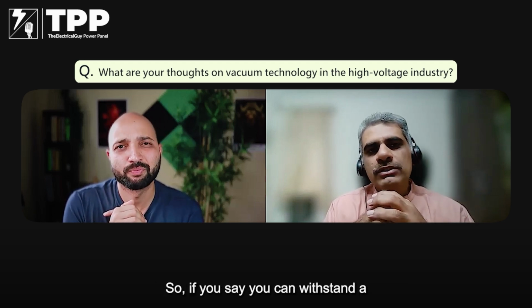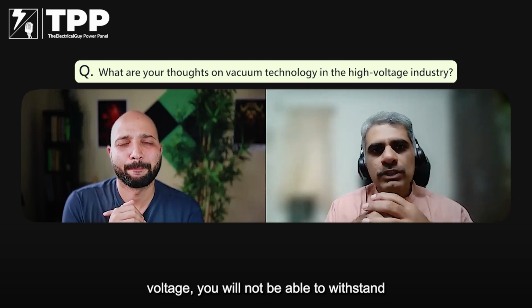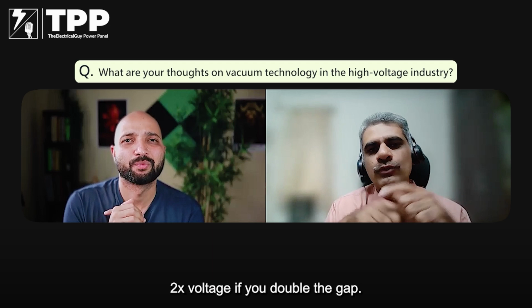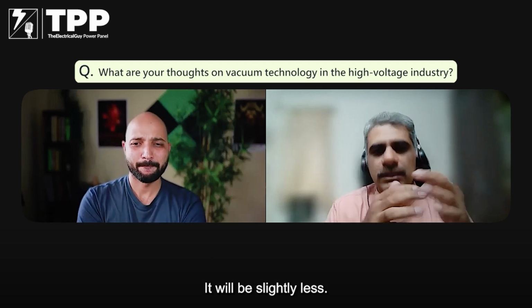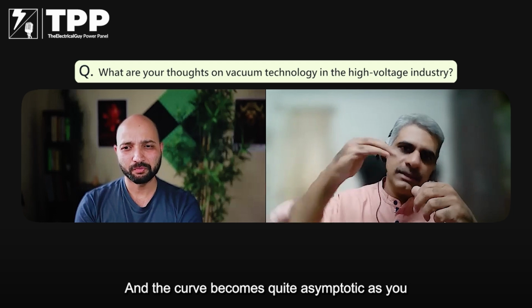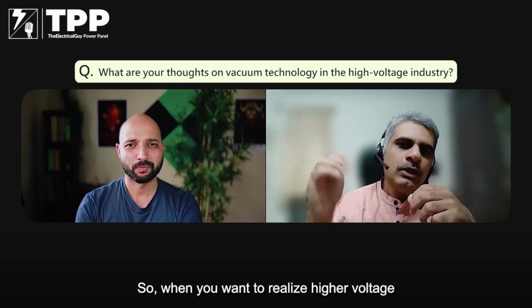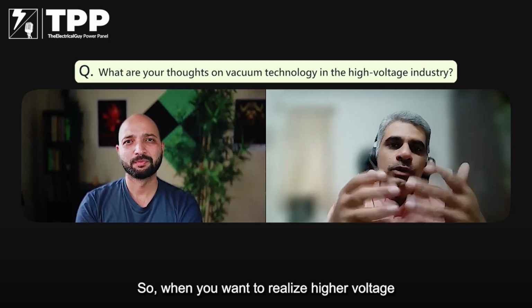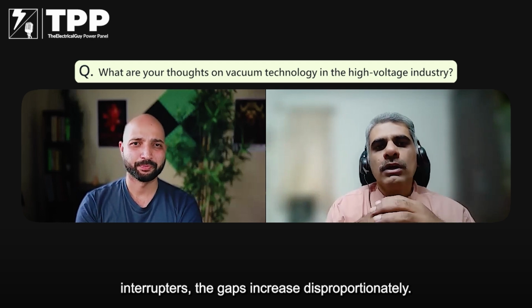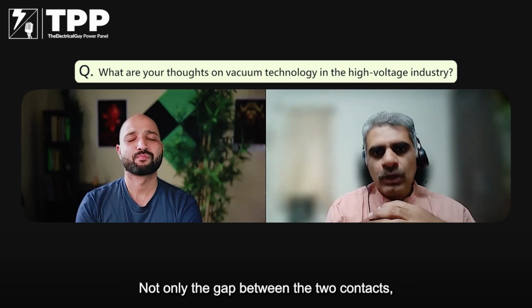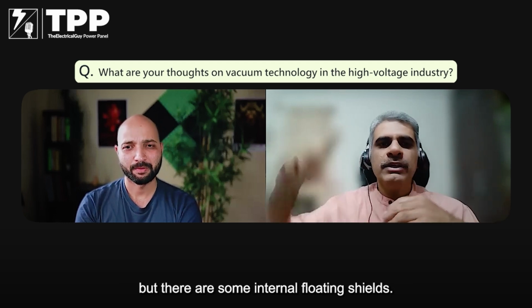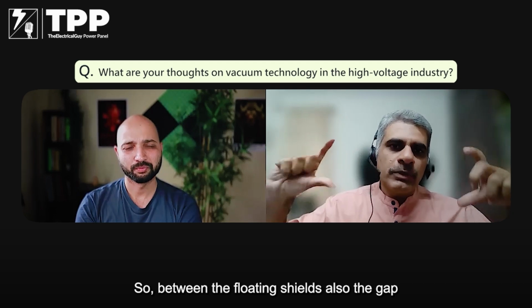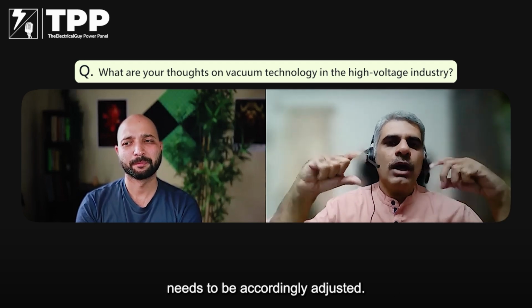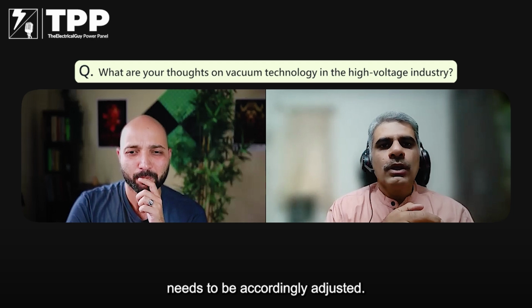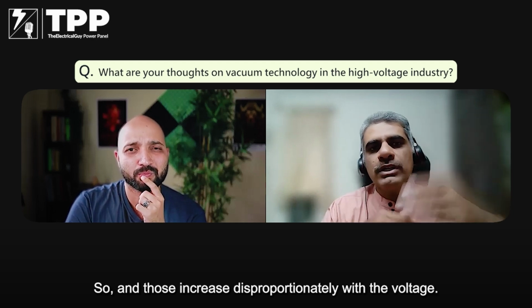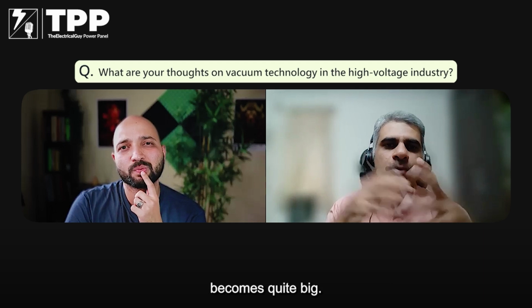So if you can withstand a certain voltage X at 6 to 8 mm, you will not be able to withstand 2X voltage if you double the gap. It will be slightly less. And the curve becomes quite asymptotic as you go higher in the gap. So when you want to realize higher voltage interrupters, the gaps increase disproportionately. Not only the gap between the two contacts, but there are also some internal floating shields. So between the floating shields also the gap needs to be accordingly adjusted. And those increase disproportionately with the voltage, and so the size of the vacuum interrupter becomes quite big.